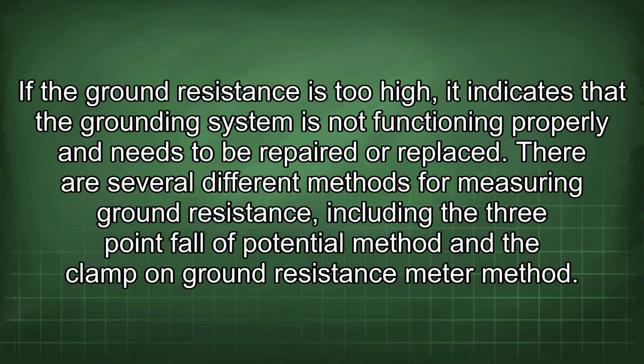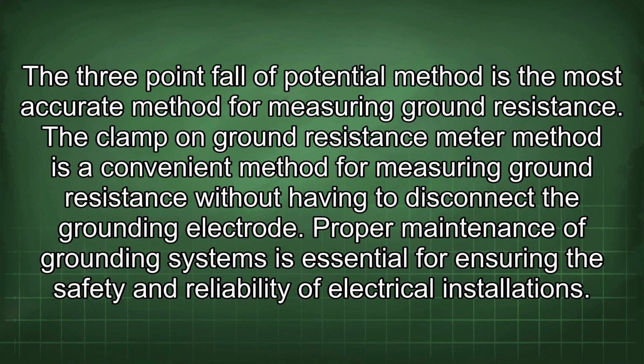be repaired or replaced. There are several different methods for measuring ground resistance, including the 3-point fall of potential method and the clamp-on ground resistance meter method. The 3-point fall of potential method is the most accurate method for measuring ground resistance. The clamp-on ground resistance meter method is a convenient method for measuring ground resistance without having to disconnect the grounding electrode. Proper maintenance of grounding systems is essential for ensuring the safety and reliability of electrical installations.